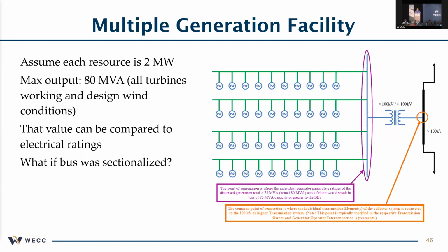This is a multiple generation facility. It's talking about, also came out of the BES definition document. It's a wind farm. And same thing. So if you assume these are 2 megawatt turbines each, max output's 80 MVA. So those connection points in that transformer, if that's greater than 80 MVA or whatever the amp rating is there, it's acceptable to limit that generation facility output to the maximum output of those, the 80 MVA for all the turbines there. If the bus were sectionalized, I asked that question there.